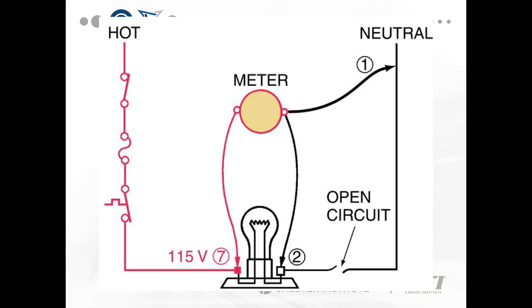Things to remember for electrical troubleshooting: use the hopscotch method — most times you'll be doing this with the circuit energized. Voltage across an open switch is source voltage. Voltage across a closed switch is zero. Resistance across an open switch is infinite. Resistance across a closed switch is zero.